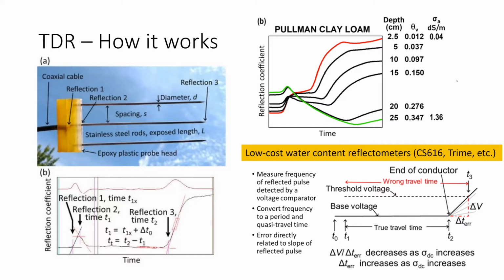Importantly, in many soils, as they get wet, they become more conductive. In this soil, as you go from 2.5 centimeters to 25 centimeters, the soil is wetter. It's also more dense, and the conductivity goes from 0.04 to 1.36 decisiemens per meter. The sharpness of the reflection at the end of the rods decreases as the conductivity increases, to the point where it may become difficult to find time 2.